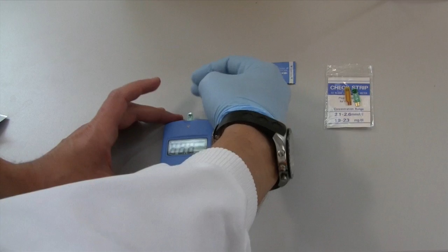When you're ready for your sample, you find the drop of blood which you're using. You then just simply rest the top of the test strip next to the blood, and as you see it will suck it up, and that's called capillary action. You then have a 1 minute time countdown, and at the end of that 1 minute the Lactate Pro will tell you the blood lactate concentration, and the units of measurement for this are millimoles per litre. So that's millimoles of lactate per litre of blood.